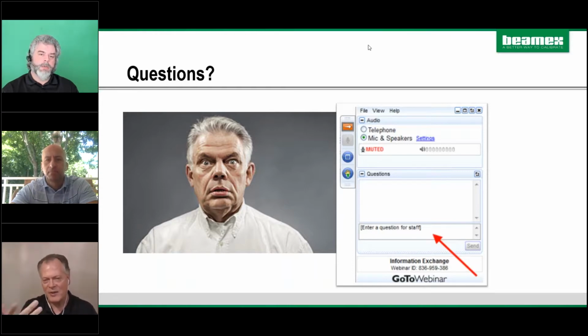We were kind of getting into that. In the RSS method, we were using accuracy numbers, and we came up with a quarter of a degree or so, but we loosened it to half a degree, which is really the best we could do with our gear, kind of backing into it. We talked about this: the tolerance needs to be whatever gives you a good quality product made in the safest and most efficient way. And giving up a little on the tolerance can save you time. So it's this negotiation of what is a good tolerance.